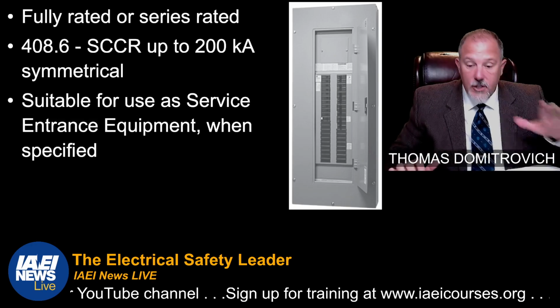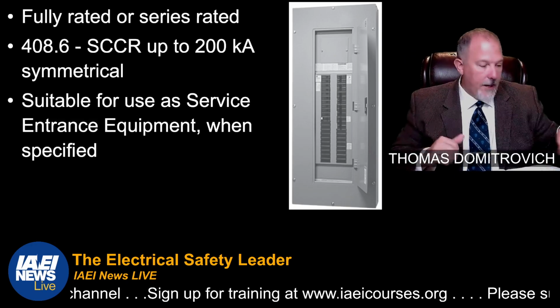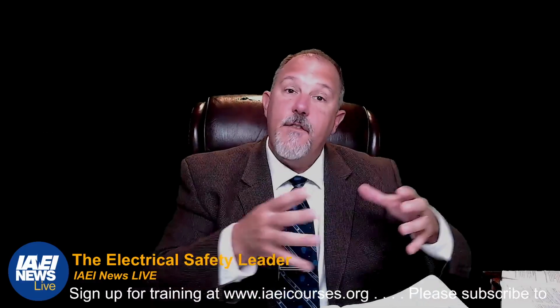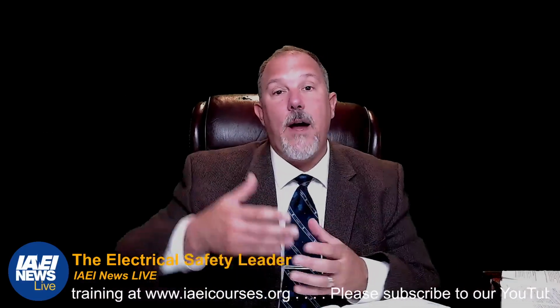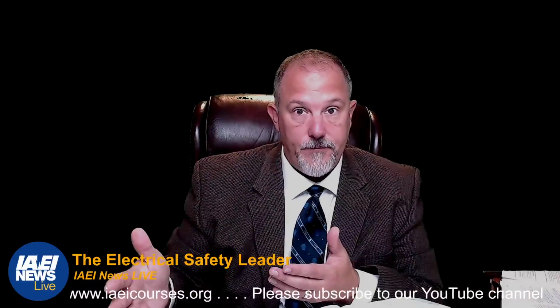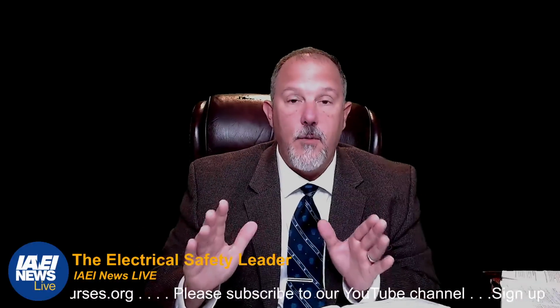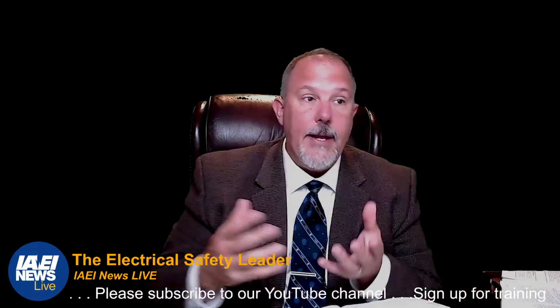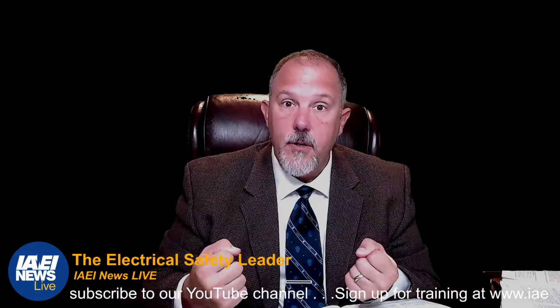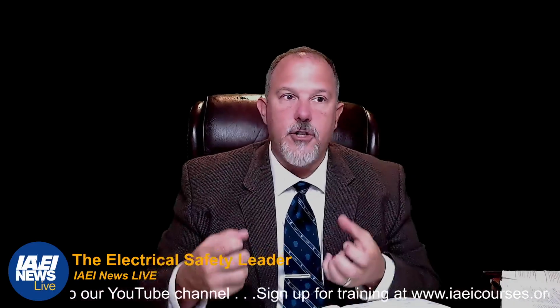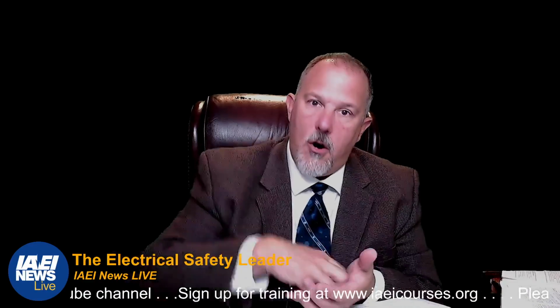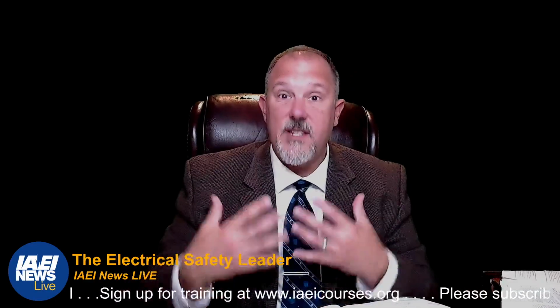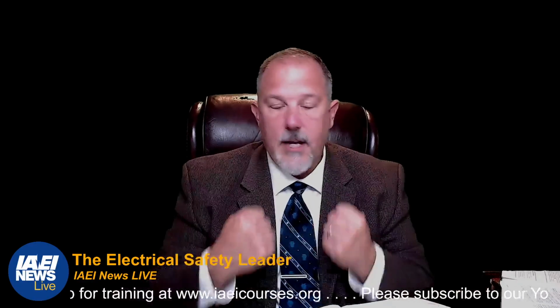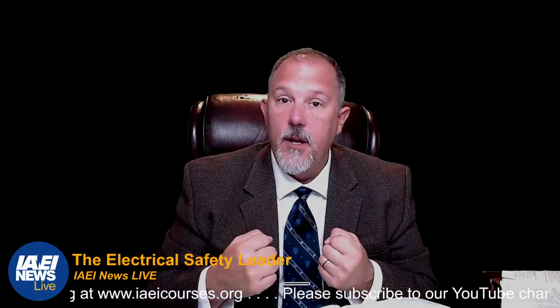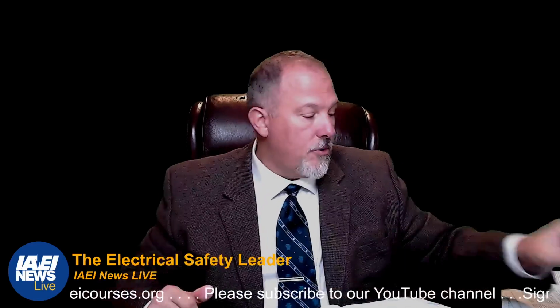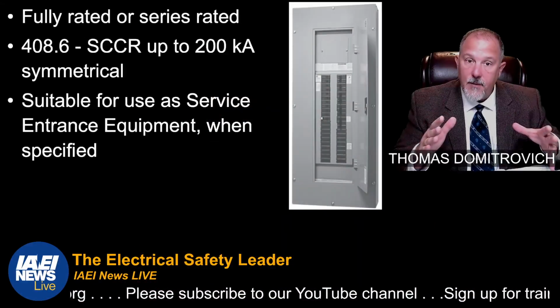Remember, what is a short circuit current rating? The short circuit current rating is the ability of the equipment to hold it together while fault current passes through it. It has nothing to do with stopping the flow of current. It is the ability of the bus structure, the mounting of the bus structure, the mounting of the components on that bus structure, being able to withstand, hold it together under the magnetic forces of pressure of the current passing through it. That's a short circuit current rating. So you can get up to 200,000 amps.